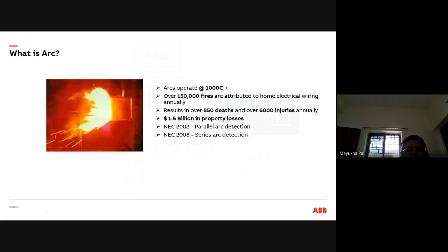So typically, arc can be a series arc or a parallel arc, right? So this is a series arc. If you are seeing the arc here, that is already showing for you. It is due to loose connections, or a breakage of a wire. So that's where you see that arc, especially from series. Parallel arc can basically be due to a short of hot or neutral. So line and ground. So again, it is of two types: line and ground, line and neutral. So you get this kind of arc.